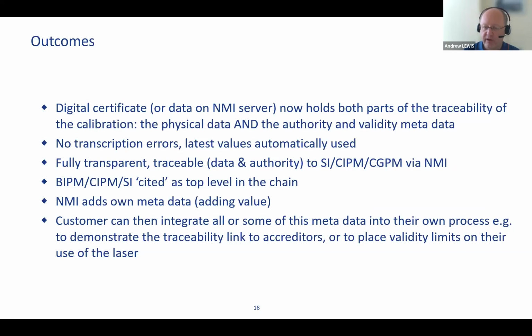It should get rid of transcription errors because the data is all encoded in machine readable format from end to end. And the software at the NMI can check that it's using the latest value by downloading it from the BIPM. It should be fully transparent. It should be traceable in terms of both the data and the authorization of the data to the SI and the CIPM. That gives an added bonus, because now the customer who receives the calibration data suddenly spots, if they look into the details, the fact that we're citing the BIPM and the SI at the top level of the chain. That can sometimes be forgotten, that there is this link between the data you receive as a customer all the way back to the SI.